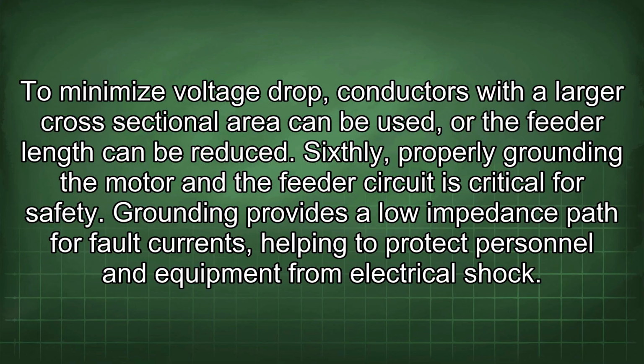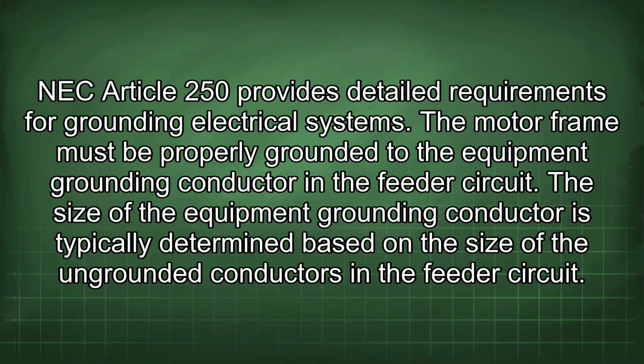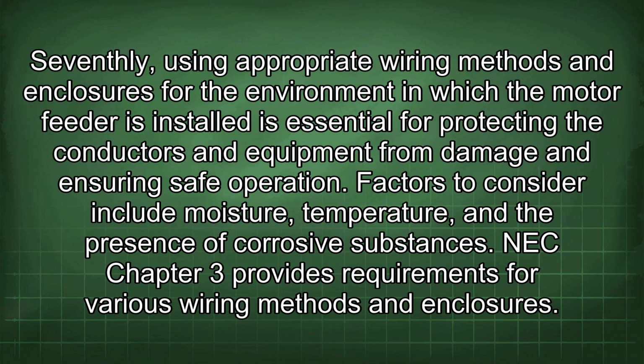Sixthly, properly grounding the motor and the feeder circuit is critical for safety. Grounding provides a low impedance path for fault currents, helping to protect personnel and equipment from electrical shock. NEC Article 250 provides detailed requirements for grounding electrical systems. The motor frame must be properly grounded to the equipment grounding conductor in the feeder circuit. The size of the equipment grounding conductor is typically determined based on the size of the ungrounded conductors in the feeder circuit.